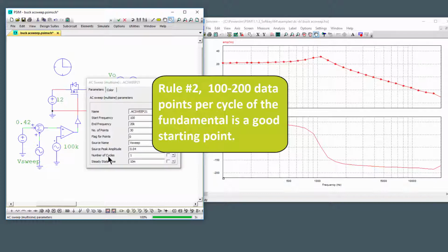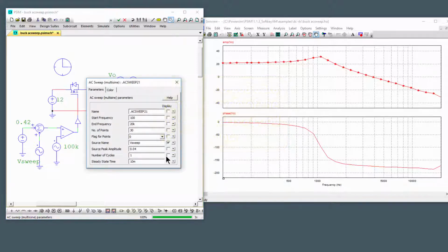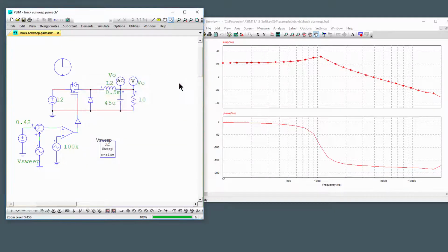And the other thing to think about is amplitude here. If we have a really small amplitude of perturbation, we need to always consider the frequency that we're actually injecting. I'll keep on hammering this point home: we're injecting real frequencies and we need to extract that data. We have 40 dB of attenuation up here. We need to make sure that there's signal left for us to measure.